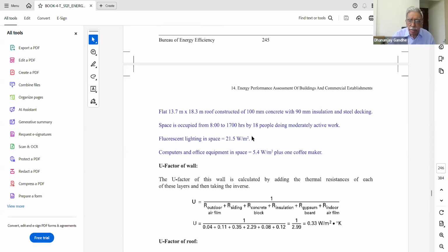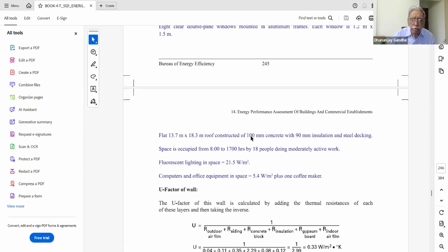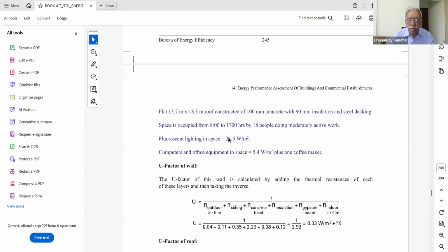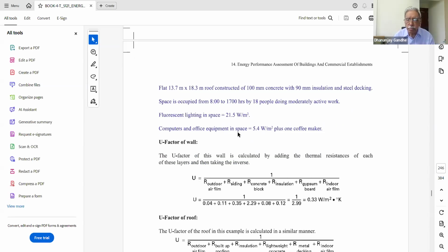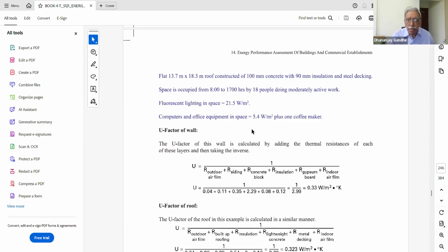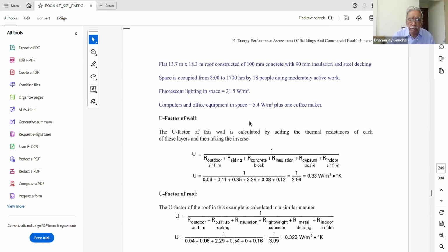so these calculations will be given later on. The values given: area is 13.7 multiplied by 18.3. The space is occupied from 8 o'clock to 5 o'clock in the evening by 18 people. Lighting load is 21.5 watts per meter square. That is the lighting power density. The computers and other equipment load is 5.4 per meter square. So these are the figures, values given here.